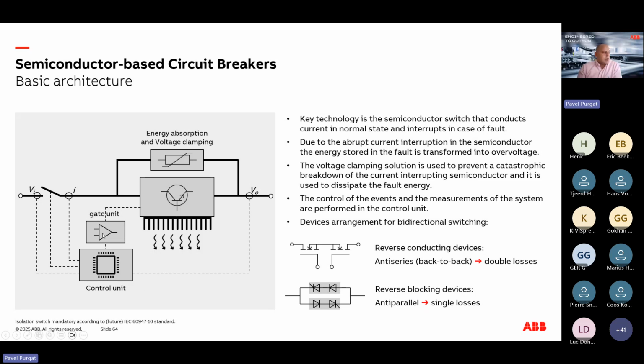And of course, some control units that are important. What usually influences the performance of the solid-state circuit breaker is how we arrange the semiconductors in the main part. A very common arrangement is using an anti-series combination of switches, or you can use a single switch and surround it with four diodes, so with a diode bridge. In this case, you always have multiple semiconductors in the path of the current. Now, in some applications this is not a problem, but in applications where efficiency is the key, this becomes a problem. That's why having an anti-parallel combination of reverse blocking devices, like shown here, can be very advantageous, because the efficiency is highly increased.